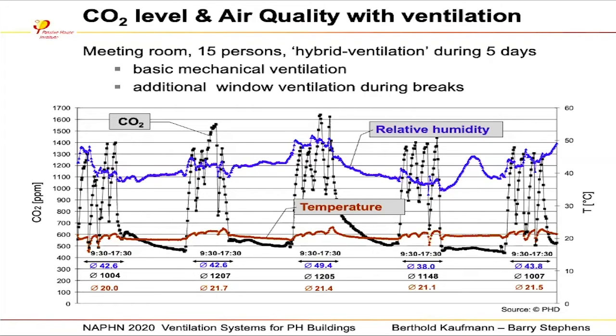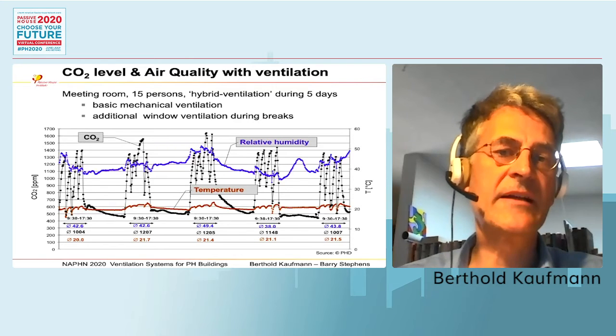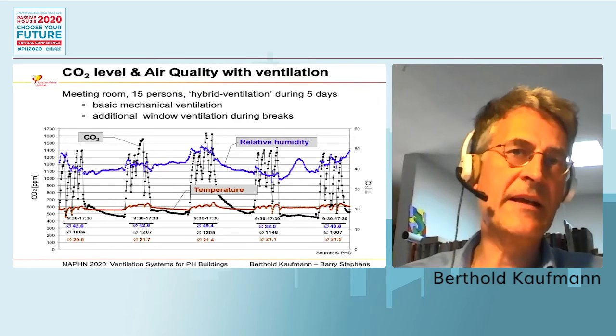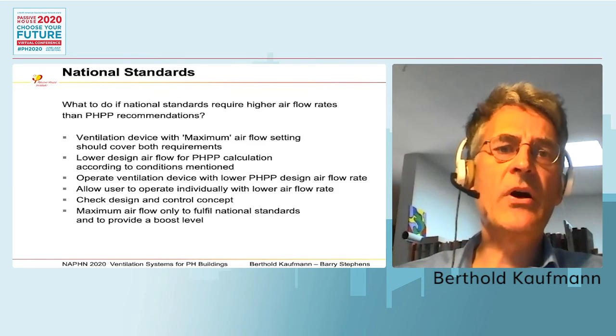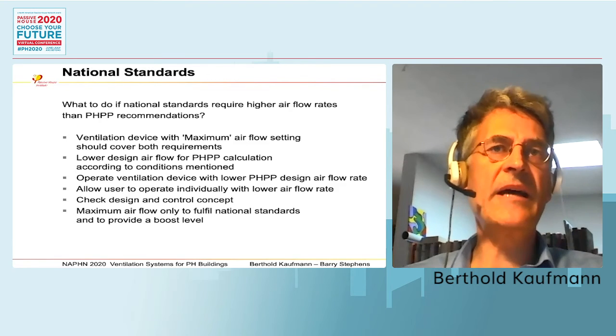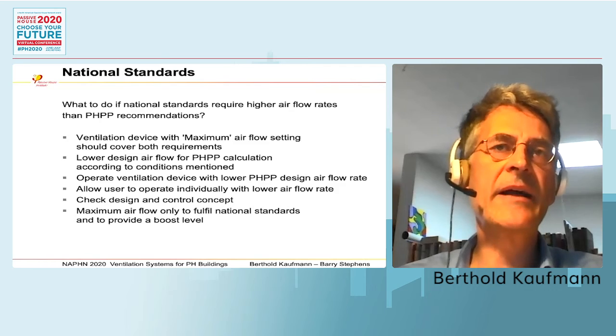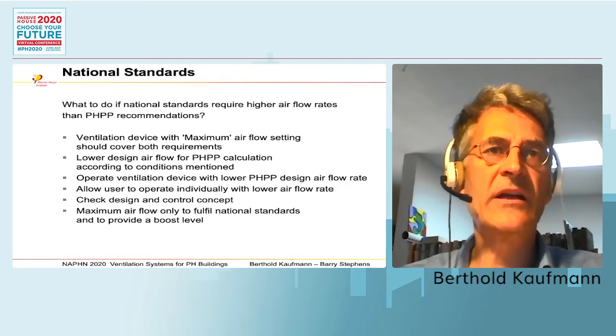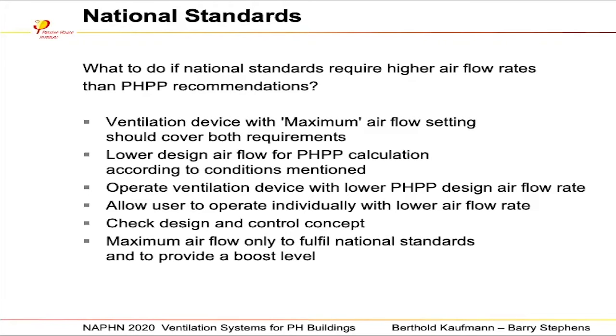Well, and with that, we come to the question, what is about the air change rate in national standards, how to deal with passive house on the next slide. And the point is, many national standards ask for more and higher ventilation rate than we recommend. Yeah, you remember we recommend about 30 cubic meters per hour, and the German standard and Austrian standard and many others, and I think the US as well, they require for much more airflow. And so the point is you must have a compromise.